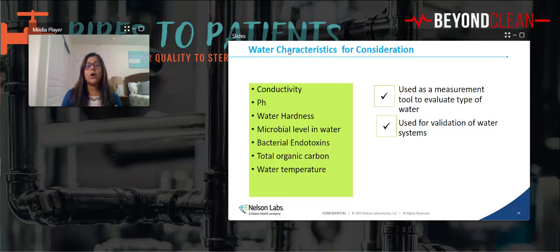These are water characteristic considerations, just some of the things, not a whole list. If I listed everything it would be a lot, but your standards, AAMI TR34 and the upcoming ST108, have very well-defined criteria for each of these measurements: conductivity, pH, water hardness, microbial level in water, bacterial endotoxins, total organic carbon, and water temperature.